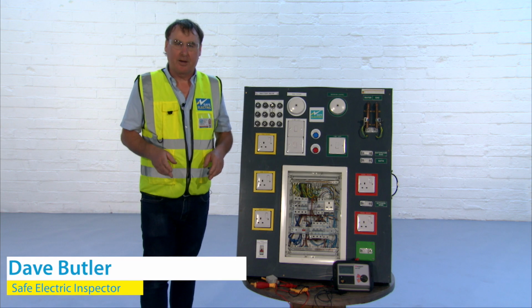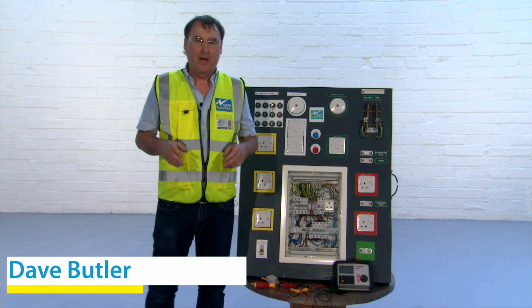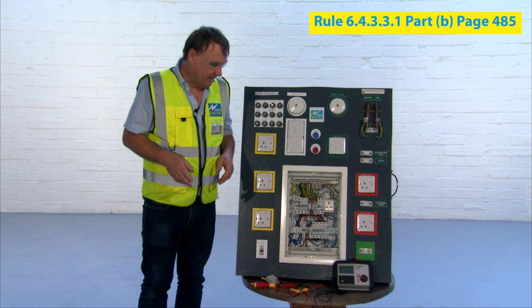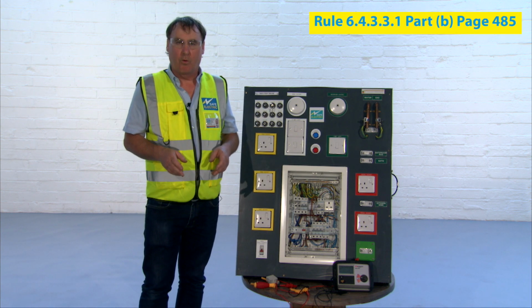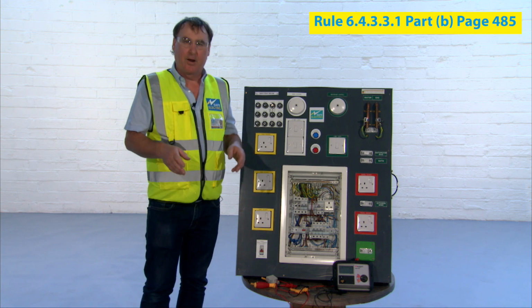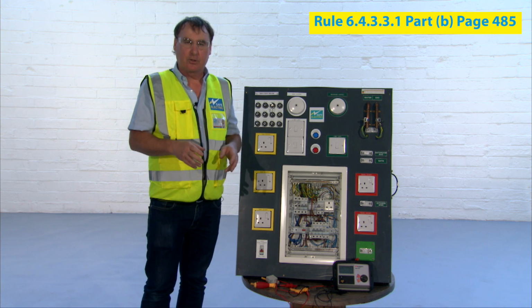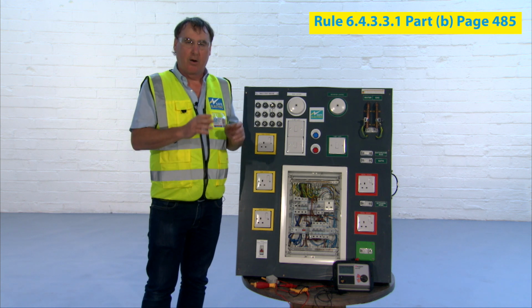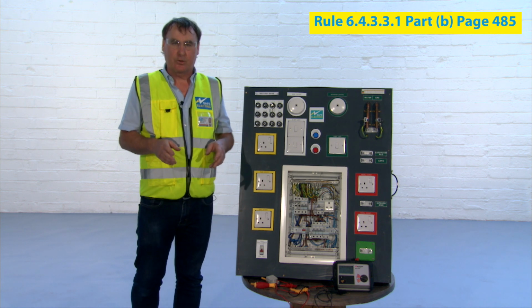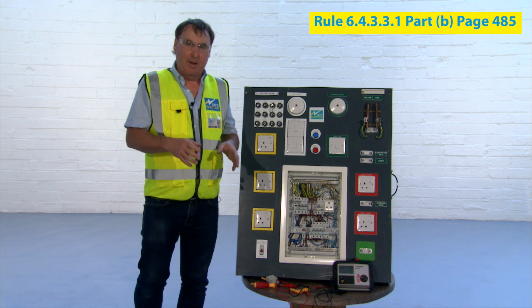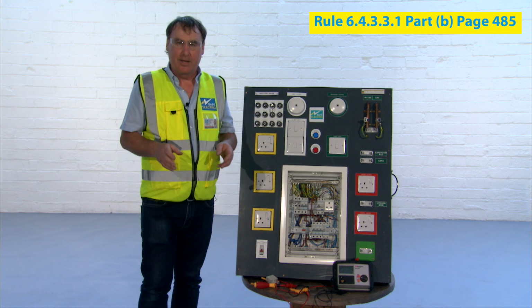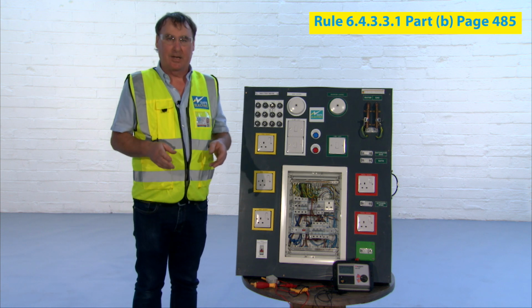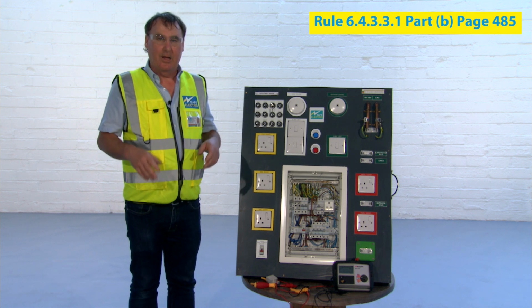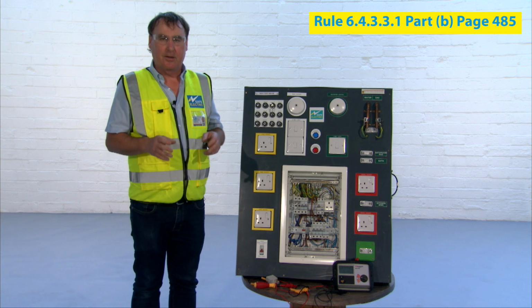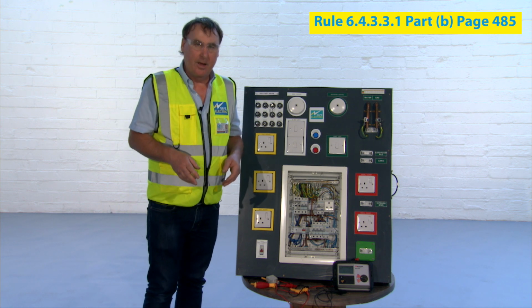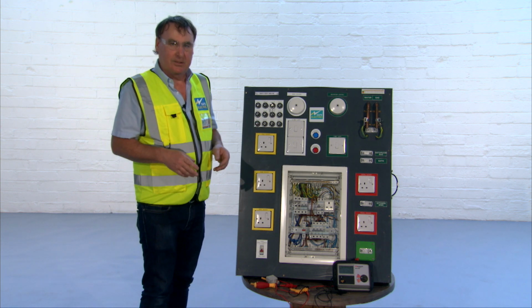I'm now going to demonstrate how to quickly and safely carry out an insulation resistance test according to IS 10101. We're going to demonstrate here a live conductors to protective conductor, or live conductors to earth, insulation resistance test today. This method can be used safely in all installations, including existing installations, and as long as it's done correctly, you will not and cannot damage existing equipment. There are basically four steps to carrying out this test.